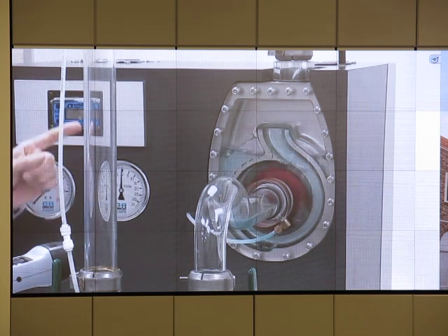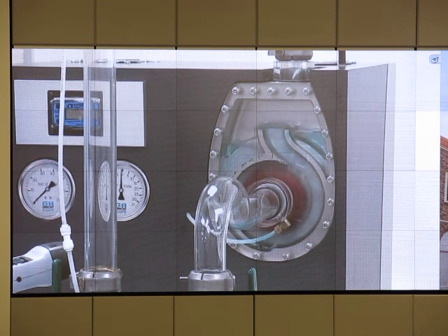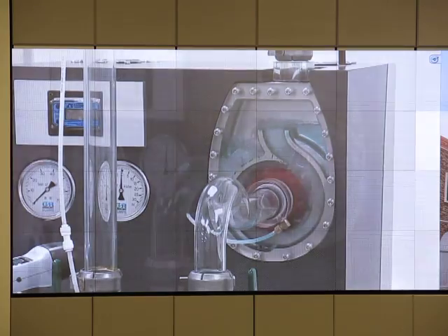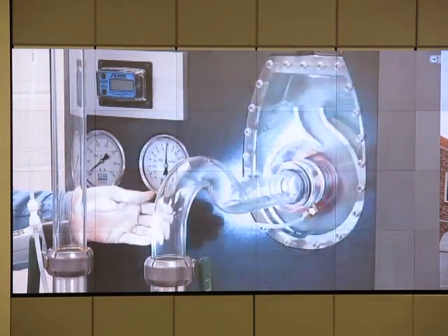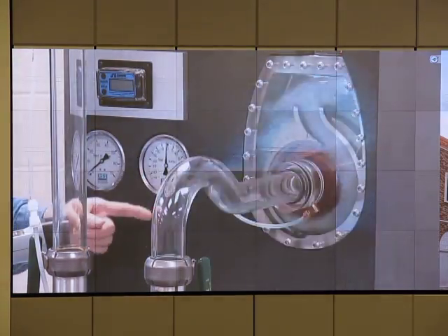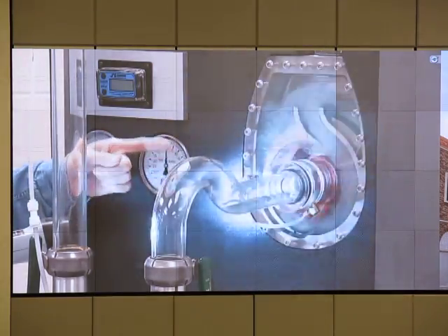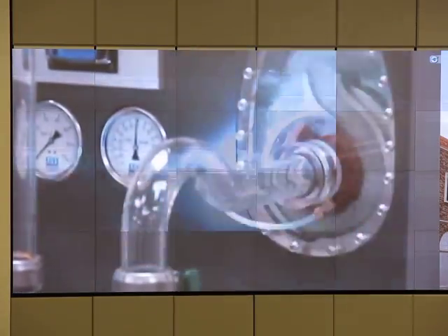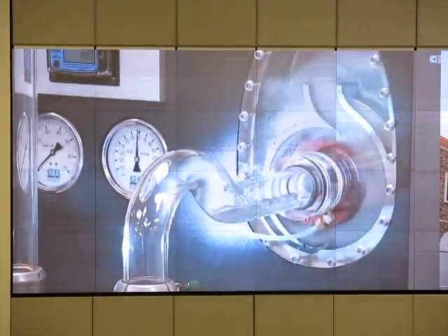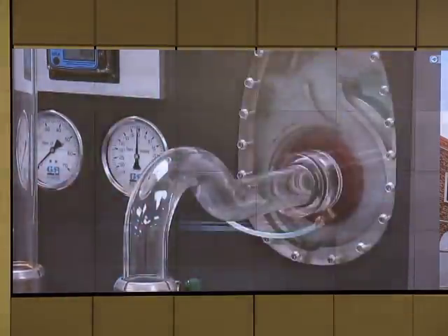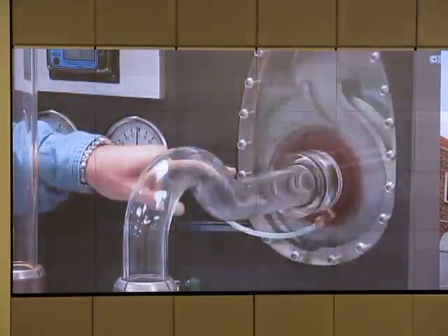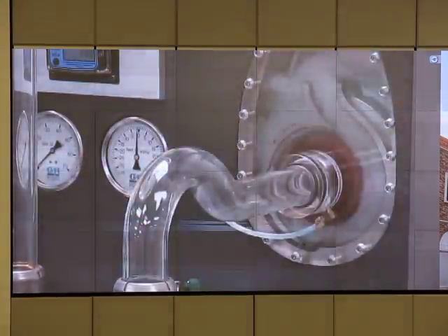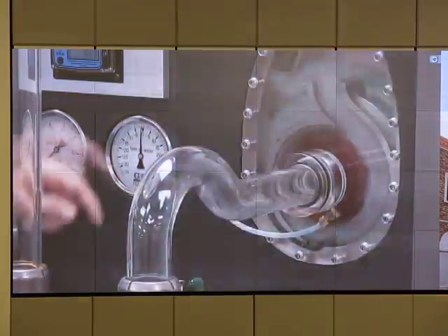Let's see what actually occurs inside of the pump during priming. After we fill the volute casing with water and we energize the pump, the impeller turns in a counterclockwise rotation. The initial prime of the pump is slung through the volute scroll, or the ever-increasing water channel, into a pressure cavity or a discharge chamber inside the volute.